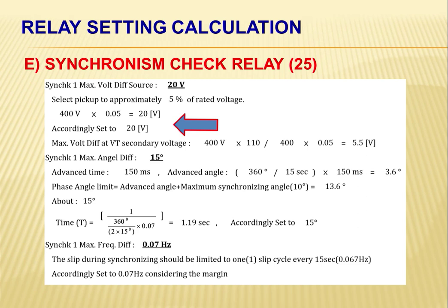And the third one, we have here the phase shift between two sources. The ideal phase shift to parallel will be 0, although that is not usually practical. Typically, phase angle limits for paralleling two sources are plus or minus 10 degrees or less. That's why here we assign the maximum synchronizing angle to be 10 degrees. We are using the maximum value, 10 degrees, from here.